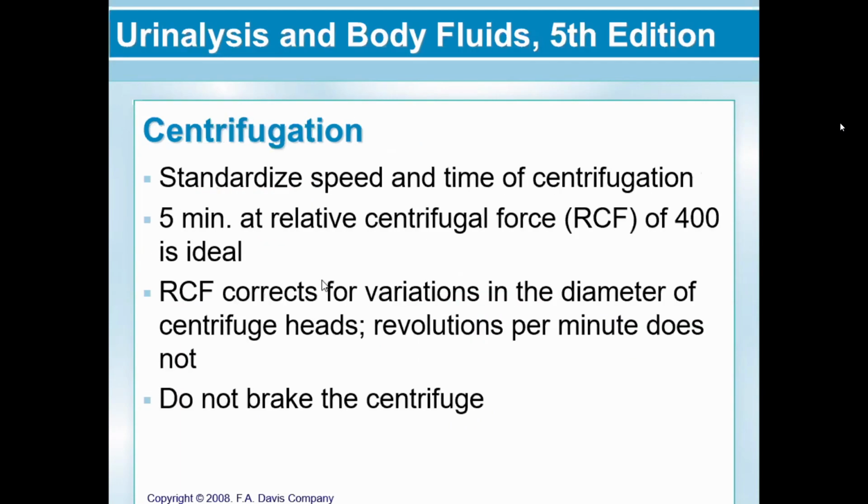So next, we have centrifugation. We standardize the speed and the time of centrifugation. It's usually 5 minutes at 400 RCF. We use relative centrifugal force instead of revolutions per minute to correct for the variations in the centrifuge head's diameter.